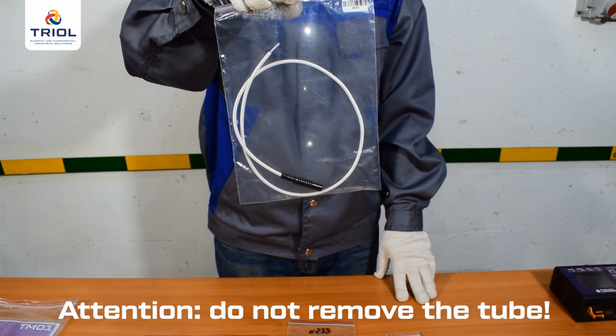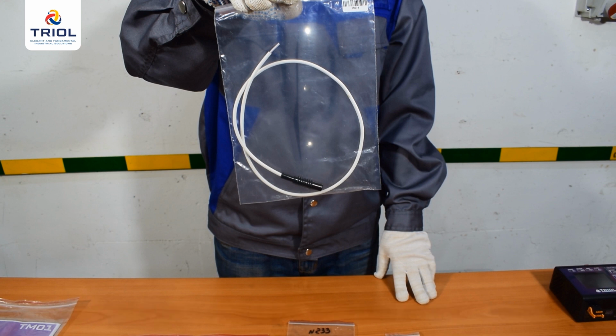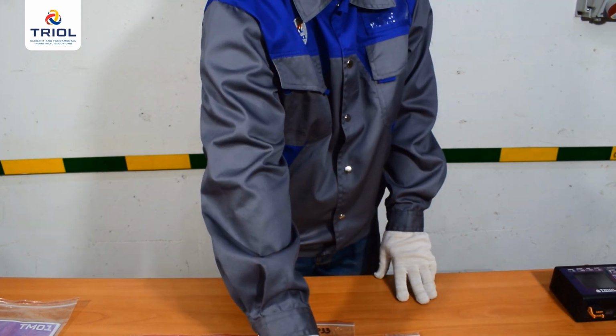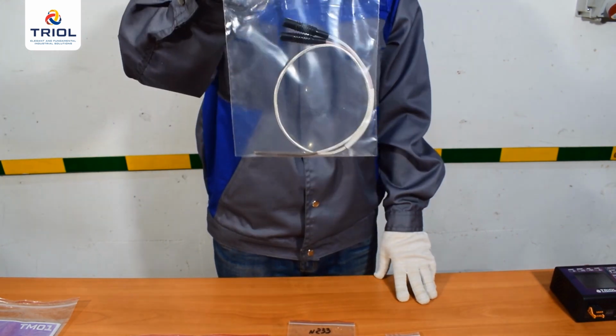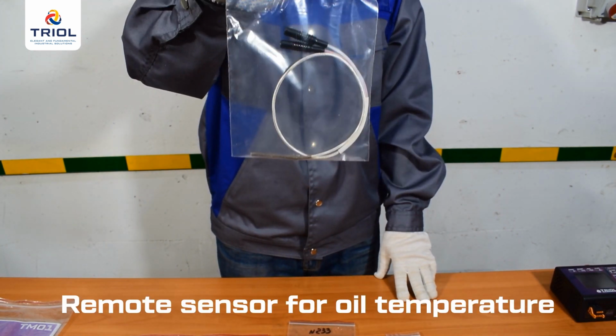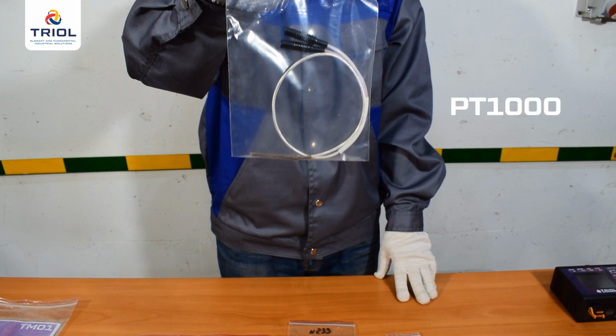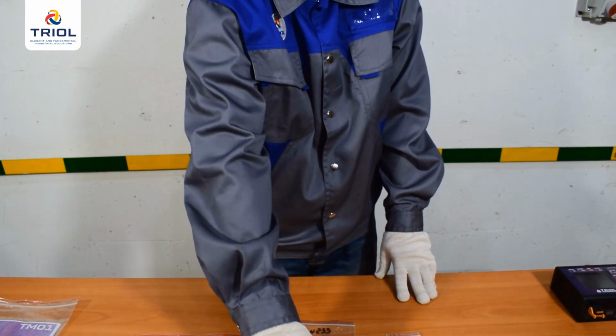Attention! Do not remove the tube. At one end the wire has a female crimp connector, while the free end is stripped to a length of 0.4 inches or 10 millimeters. Remote sensor for oil temperature of the submersible electric motor. The delivery set can optionally include both a Type J thermocouple and a PT1000. This video shows a PT1000. The sensor comes in a set ready for installation. No additional operations such as crimping or soldering are required.